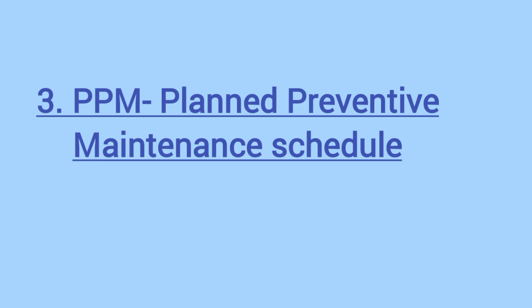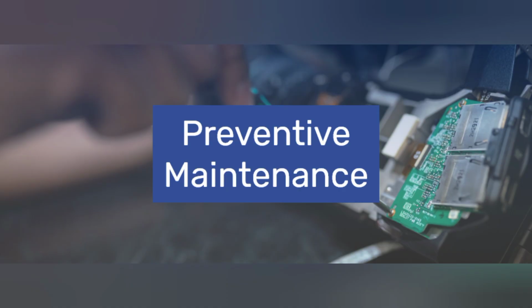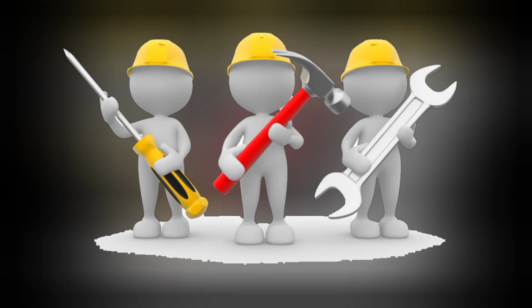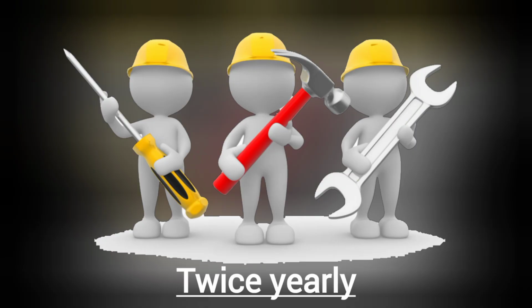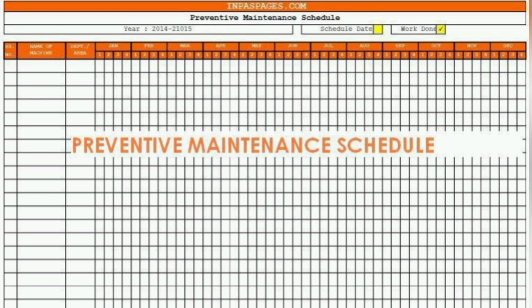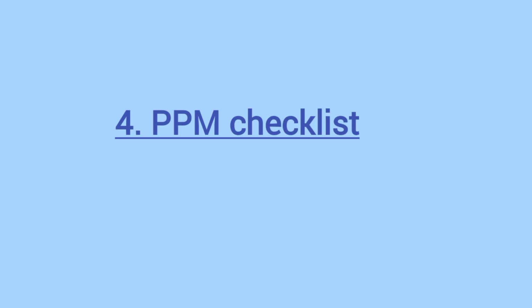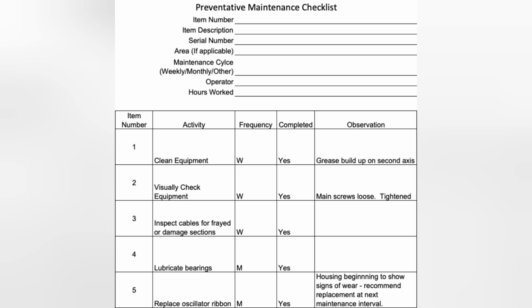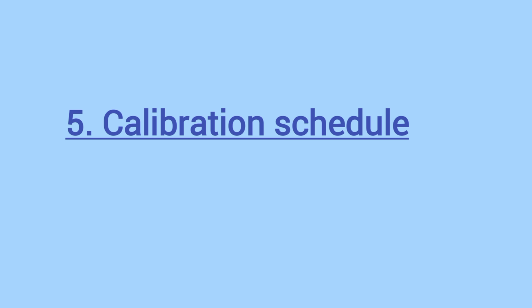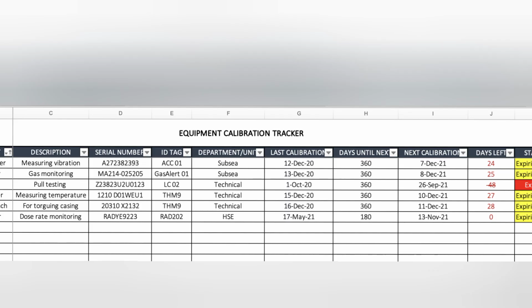The long form of PPM is planned preventive maintenance. Every equipment should go under preventive maintenance a minimum of twice a year. So you should maintain a planned dated schedule for servicing and maintenance. The fourth file is the PPM checklist. Again, a planned maintenance list. It would guide you whether your maintenance is done or not. Mention your maintenance performed date in the list for better guidance. Fifth is the calibration schedule. Like the PPM schedule, you need to maintain a calibration schedule also. It should be done once a year.